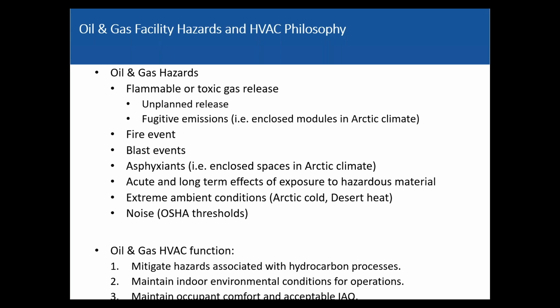Guys who are running pigging operations, they're getting blasted with hydrocarbons every time they open it up. Extreme ambient conditions, noise. Don't often think about noise, but really loud processes, people go deaf. So something to be aware of. And then what is oil and gas HVAC's main function? Well, number one, mitigate the hazards associated with the hydrocarbons. And number two, maintain the indoor environment so that operations continue. So our sprinklers don't freeze, and the equipment doesn't fail. Way down here at number three is maintain occupant comfort.